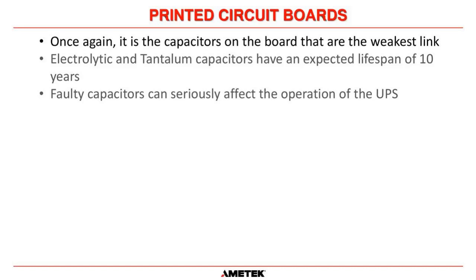So faulty capacitors can seriously affect the operation of the UPS. They're usually used in power supplies on control boards and for other circuits within the UPS. If they fail, they can cause unpredictable operation of the UPS and can cause you to be in bypass when you don't want to be in bypass. And then if you do have an AC power failure at that time, you will drop the load. So we always recommend that the circuit boards are replaced every 10 years, but that is mainly due to the DC electrolytic capacitors on those boards.